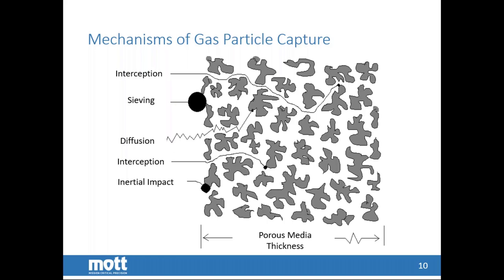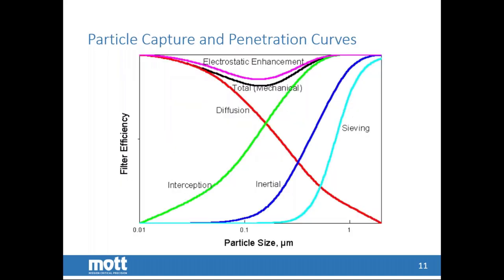The next larger particle size would be captured by inertial impaction. That means that the particle size is large enough so that it has enough mass and its inertia will cause it to flow out of the gas stream and impact the porous material. And of course, for the very large particles in gas filtration, sieving is also a mechanism. This graph shows the effect of particle size on filtration efficiency. The filter efficiency for diffusion is very high for small particle sizes and continues to trend downward as particle sizes increase. Whereas with sieving on the other end of the spectrum, it is very efficient at very large particle sizes and not as much in the smaller particle sizes.